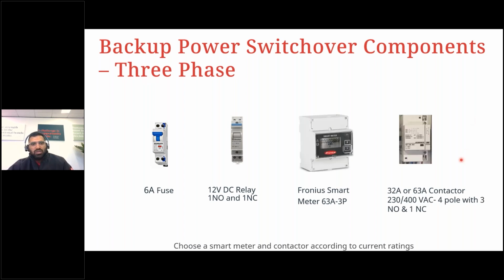So when it comes to three-phase, it's exactly the same. The only difference here is you have a three-phase meter and a breaker that can control 3 phases. So 3 normally open and 1 normally closed. The relay has 1 normally open, 1 normally closed. Again, choose the meter and the contactor depending on the current. So here as just an example, 63 amps, but you might need to consider using a 50K smart meter if you are trying to control something larger than 63 amps, for example.